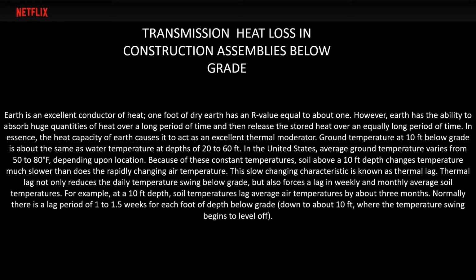Because of these constant temperatures, soil above a 10 feet depth changes temperature much slower than the rapidly changing air temperature. This slow changing characteristic is known as thermal lag. Thermal lag not only reduces the daily temperature swing below grade but also forces a lag in weekly and monthly average soil temperatures. For example, at a 10 feet depth, soil temperature lags average air temperature by about 3 months. Normally, there is a lag period of 1 to 1.5 weeks for each foot in depth below grade, down to about 10 feet where the temperature swings begin to level off.